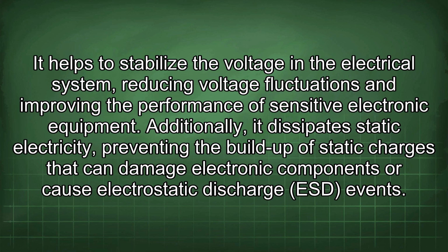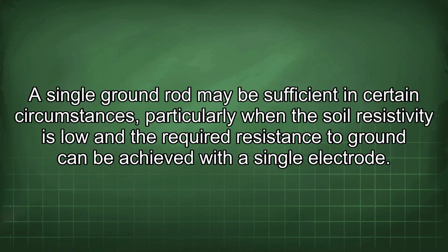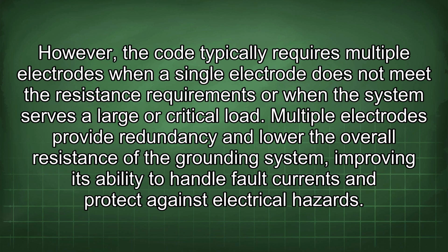A single ground rod may be sufficient in certain circumstances, particularly when the soil resistivity is low and the required resistance to ground can be achieved with a single electrode. However, the code typically requires multiple electrodes when a single electrode does not meet the resistance requirements or when the system serves a large or critical load. Multiple electrodes provide redundancy and lower the overall resistance of the grounding system, improving its ability to handle fault currents and protect against electrical hazards.